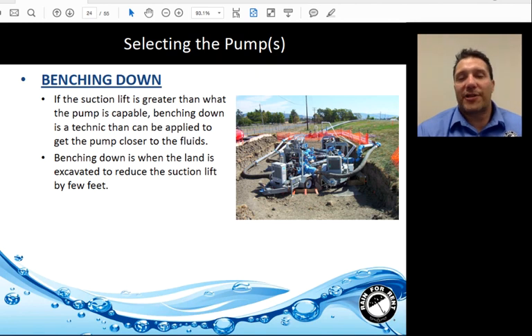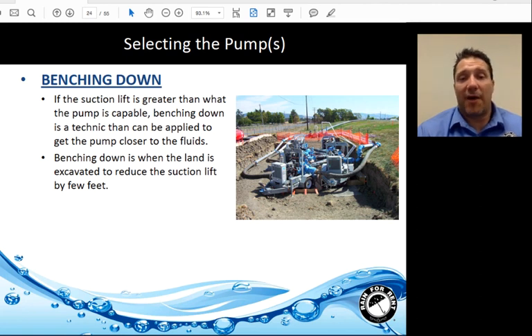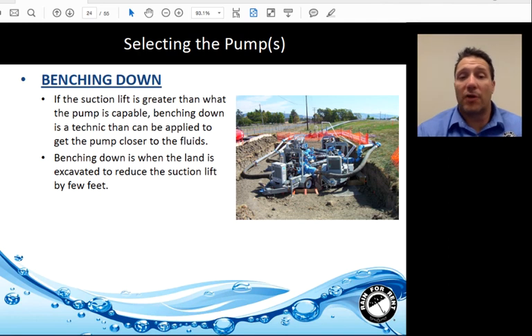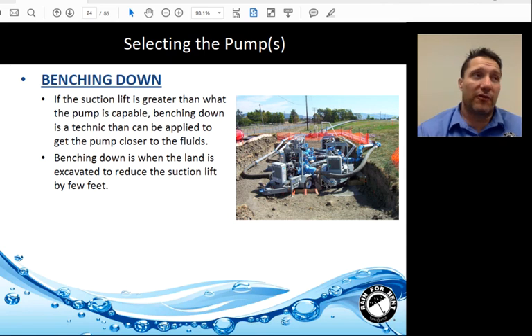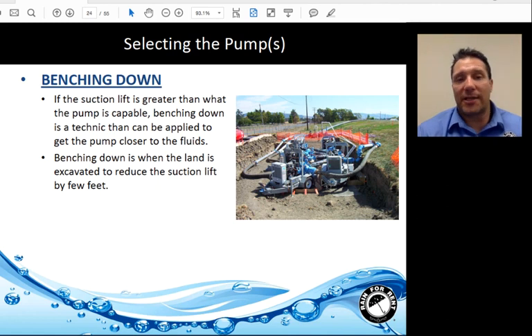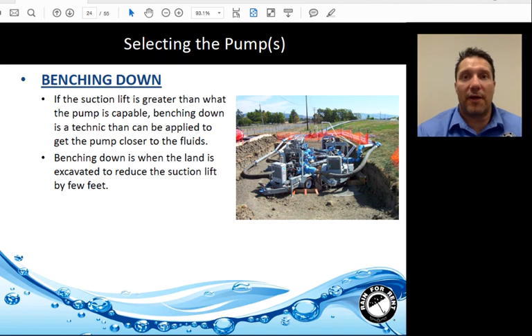In cases where suction lift is too great for centrifugal pumps, one solution is benching down — essentially digging a hole and moving your pumps closer to the fluid. Benching down moves your pumps closer to your fluid; surcharge moves your fluid closer to your pumps. Regardless of which method is employed, you are decreasing your suction lift and increasing your net positive suction head available.